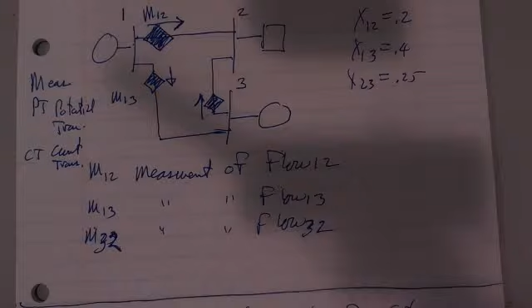They do the same thing for current. In classical cases, they did a measurement with the potential transformer and the current transformer — it literally steps down the voltage to a low value, used for protection. The relay equipment reads those PT and CT values, and we measure off of those as well. Classical ones didn't use anything with transistors; they used magnetic circuits that would give a value fairly accurately proportional to P, Q, or the voltage magnitude.